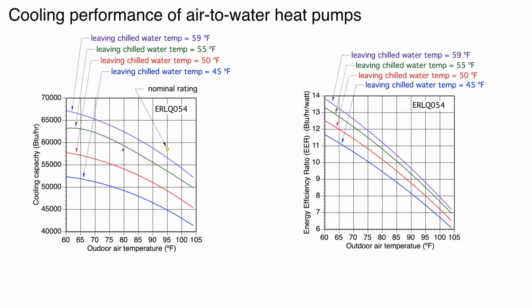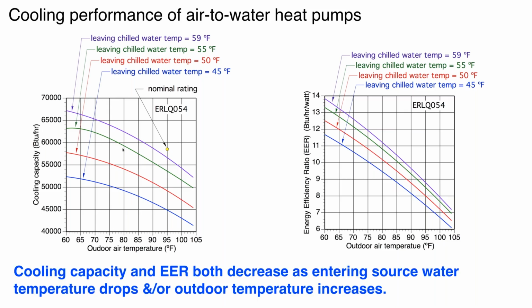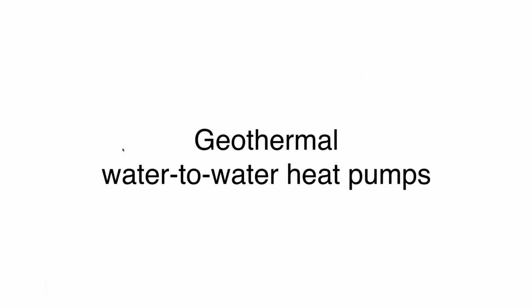And it's really the same story with energy efficiency ratio, or in some cases you'll see it stated as cooling COP. The higher the number, the better. So as it gets warmer outside, the energy efficiency ratio drops, and also it drops as we force that chill water temperature to go to lower and lower values. Okay. Now, geothermal.